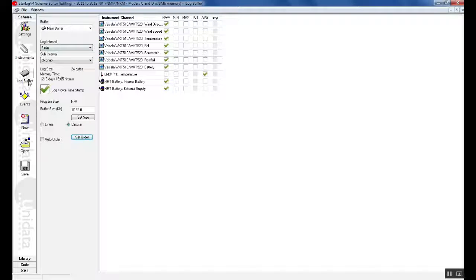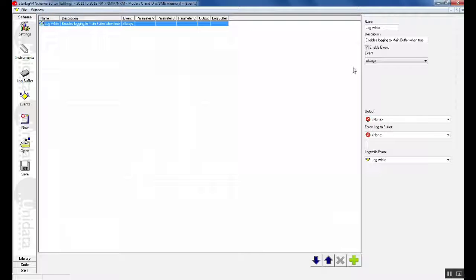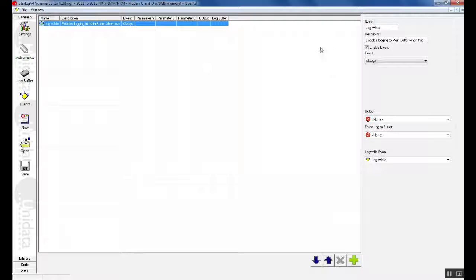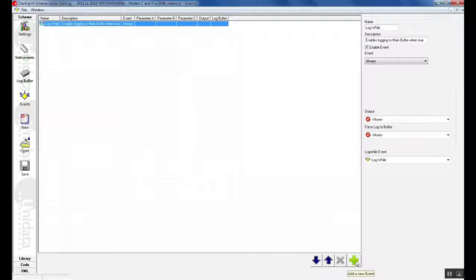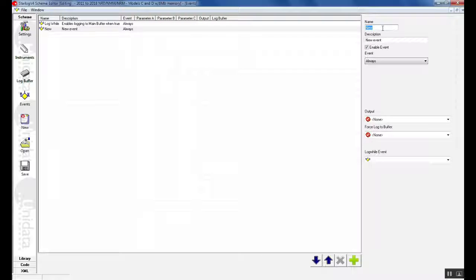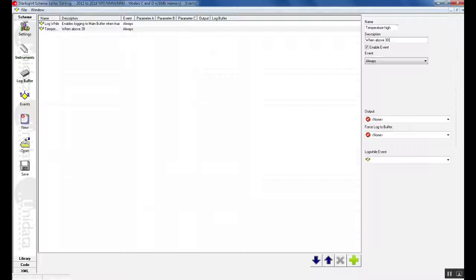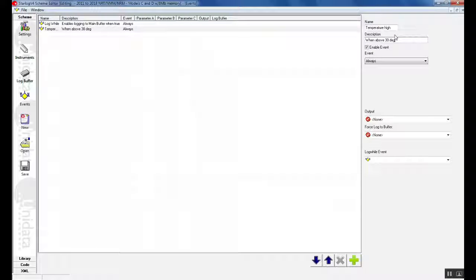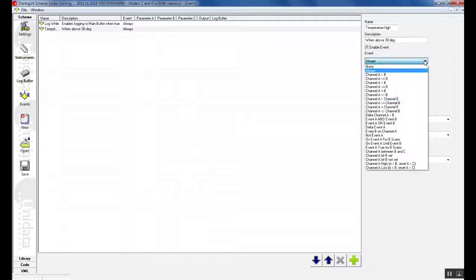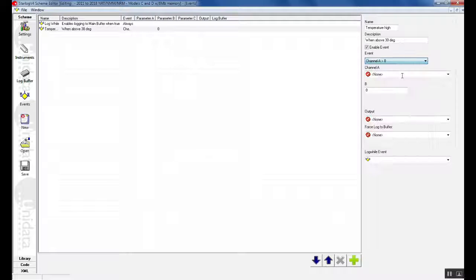In the scheme we can also add events. Events are done to record if an event has been triggered or if you would like to trigger events. The log while event must be always there so that logging is always done. In this section we will add an event just to show how it works. So in an event we have now added an event. For example we could say temperature high. When the temperature goes above 30 degrees we can trigger an event. Note that the description and the name can be anything you would like. Here we have many events. For this event we would say if the temperature is greater than 30 degrees then we would like to trigger an event.